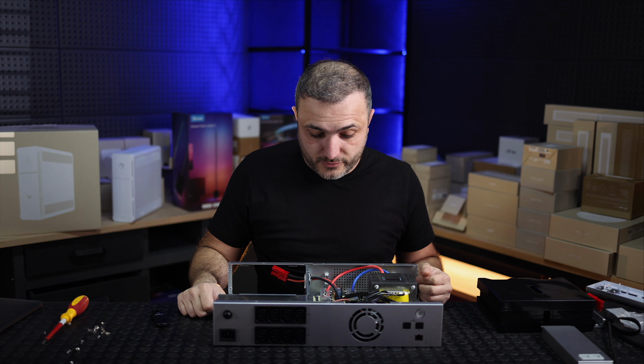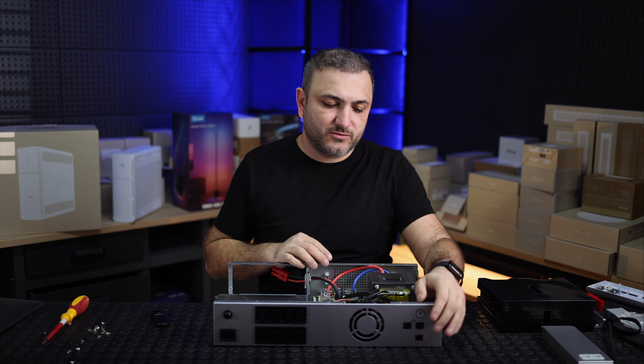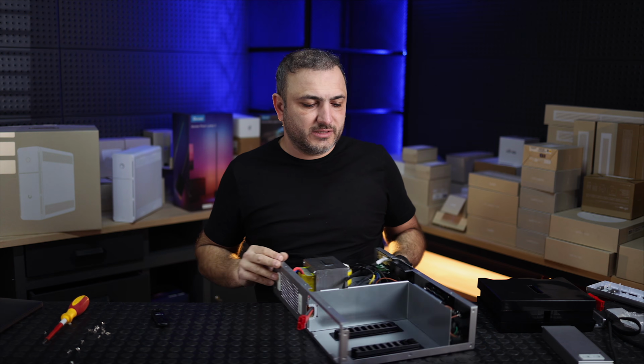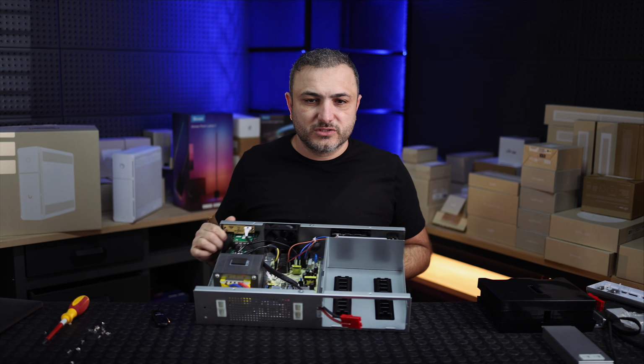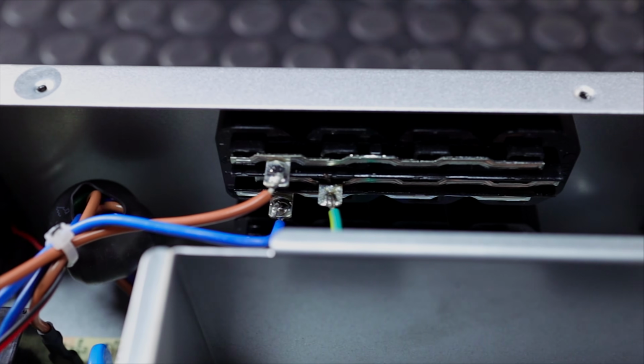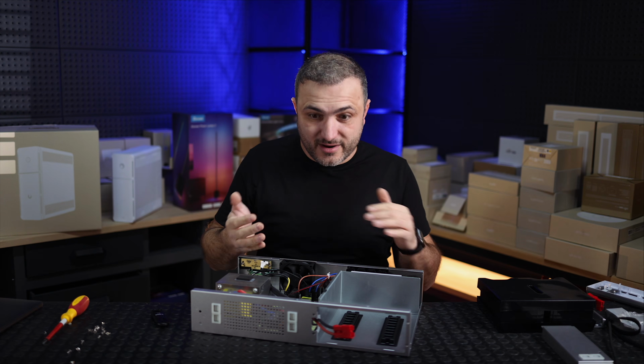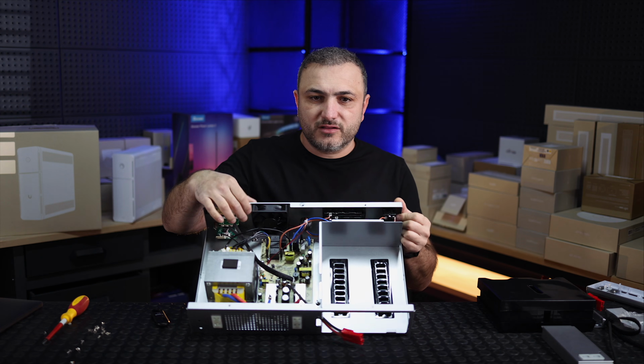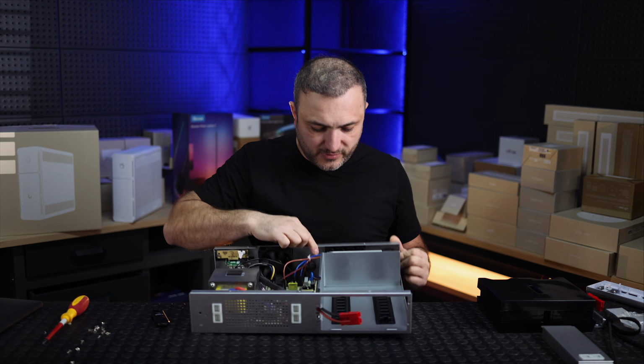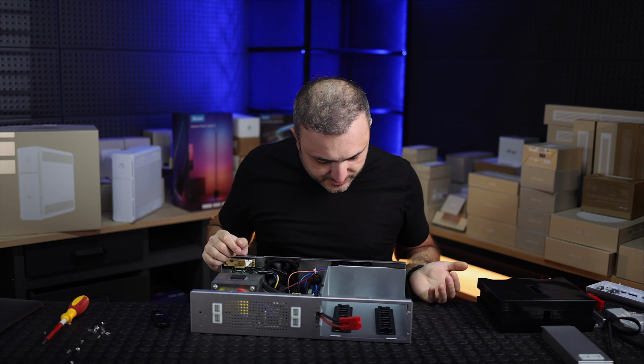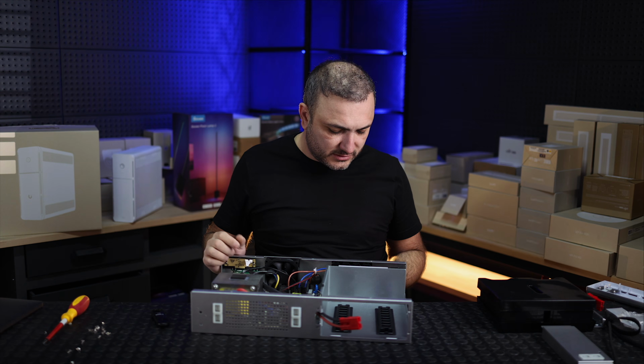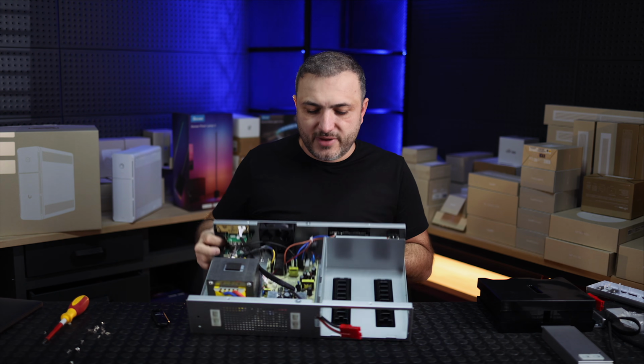And I have bad news for you: that won't be possible. Once we opened the UPS we noticed that all the outputs are connected in parallel. So basically you have only one wire that comes from the PCB, connected to this parallel array. The same applies to surge protection and to the batteries.